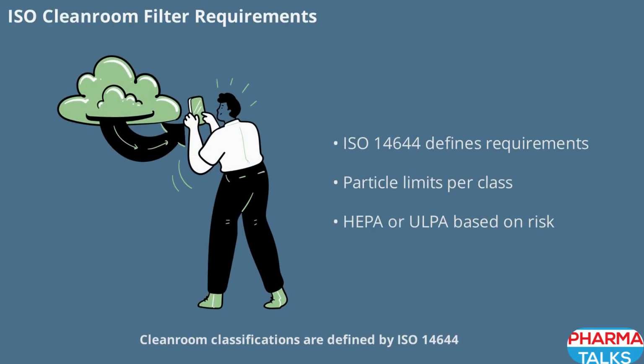Cleanroom classifications are defined by ISO 14644, which sets particle concentration limits for different classes. Depending on the ISO class of your cleanroom, either HEPA or ULPA filters may be required to achieve compliance. The choice is based on the level of risk and the specific processes taking place in the cleanroom.